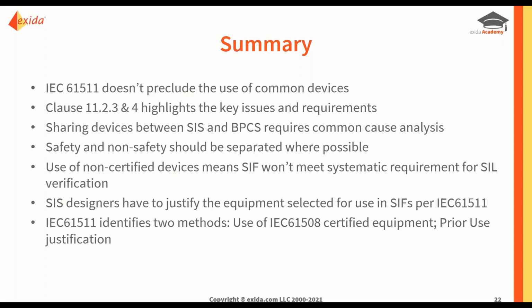SIS designers have to justify the selected equipment for use in SIFs per 1511. And it only gives you two methods. It says you can either use 1508 certified devices for the appropriate SIL, or you have to do prior use justification. Those are the only two options that you have.